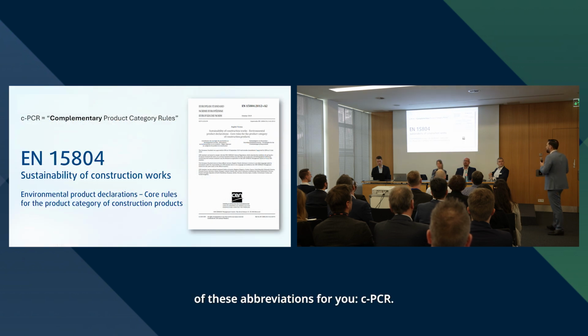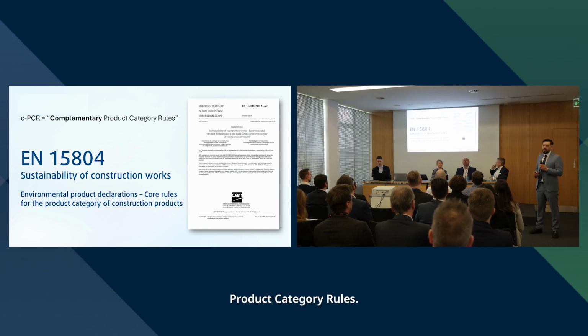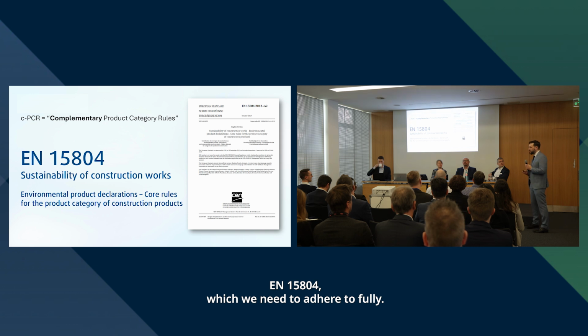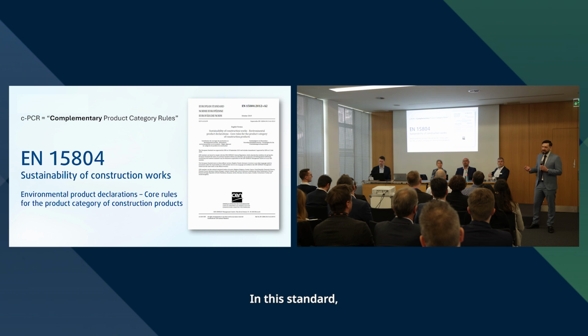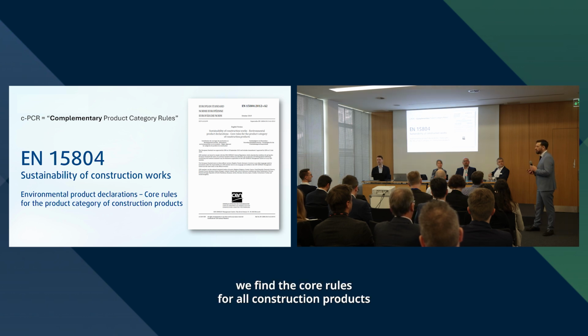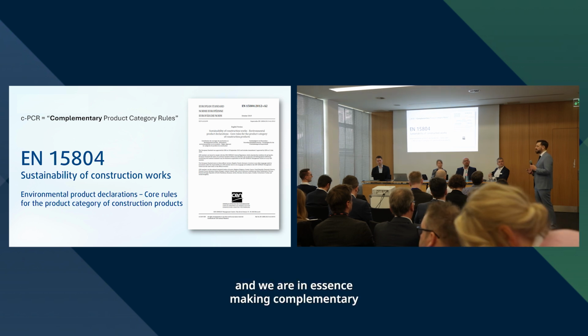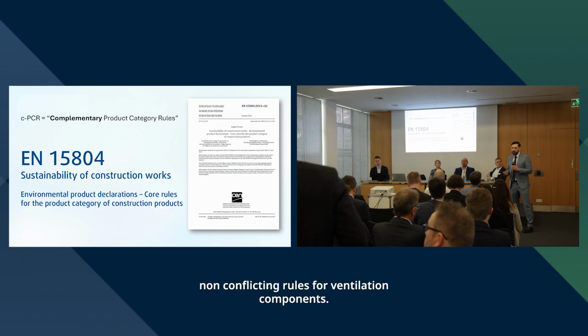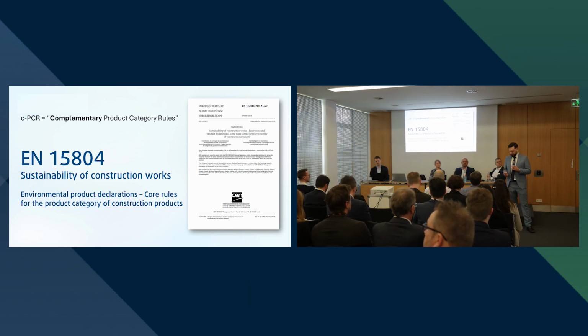So here's another one of these abbreviations for you, CPCR. CPCR stands for Complementary Product Category Rules. And complementary refers to EN 15804, which we need to adhere to fully. In this standard, we find the core rules for all construction products. And we are in essence making complementary, non-conflicting rules for ventilation components.